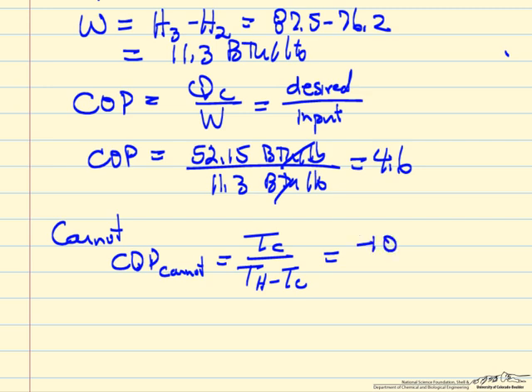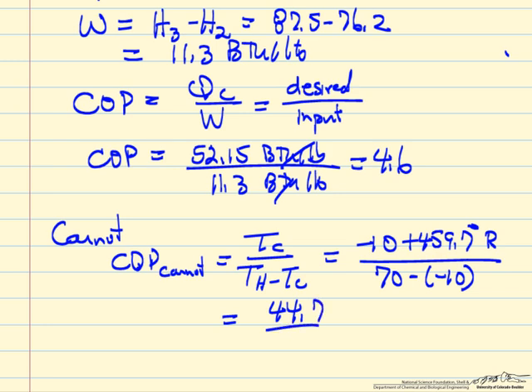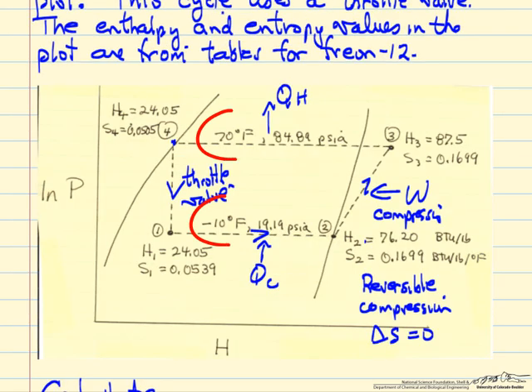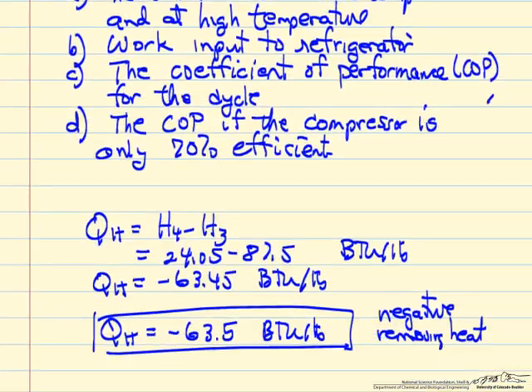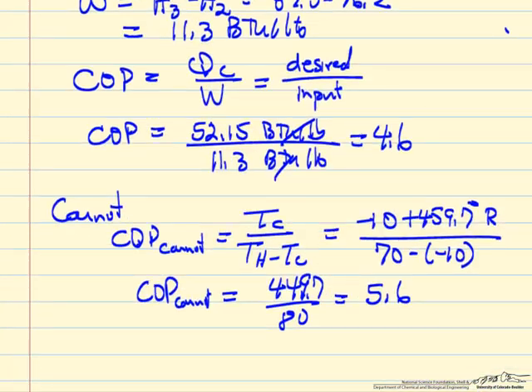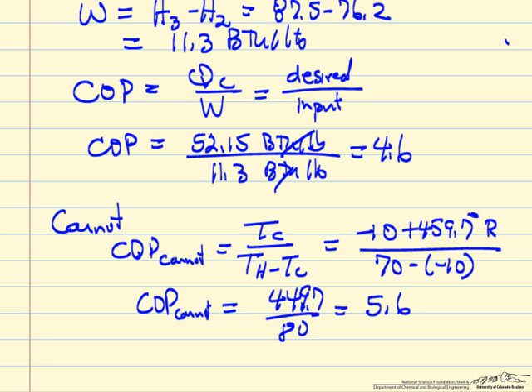So low temperature is minus 10, and we add 459.7 to make it degrees Rankine. Since we are looking at temperature differences, we don't actually have to use the absolute temperatures. So 449.7 over 80 is 5.6. The best we could do between this high temperature of 70 degrees and this low temperature of minus 10 is 5.6 if we ran a Carnot cycle between those.